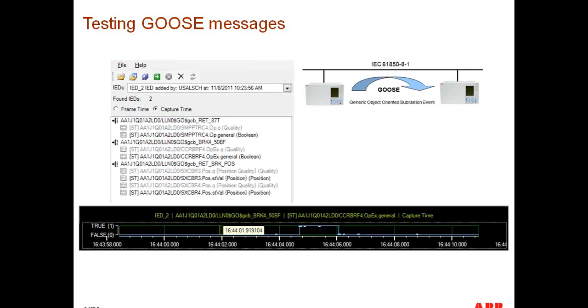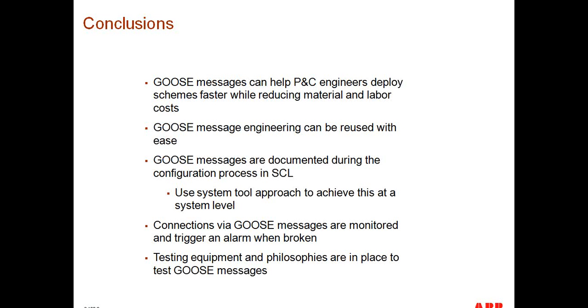We can also get a visual of when those Goose messages change state, with a timestamp, using this particular tool. The darker dots indicate when a Goose message was sent, and I can scroll on my timing bar to get an understanding of the time at which that particular message was sent, so that we can gauge performance this way.